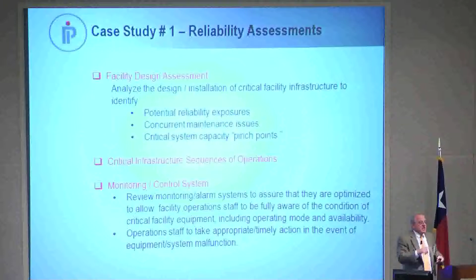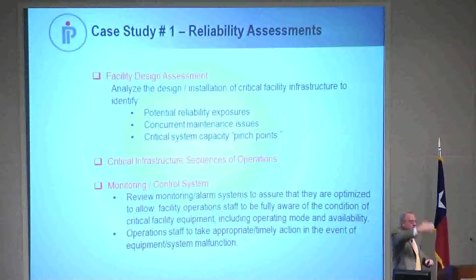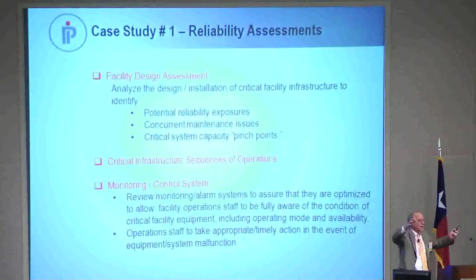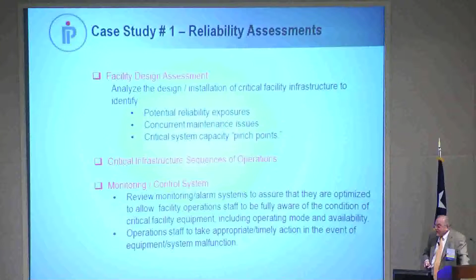It gives you an opportunity to review the sequences of operations and make sure that control package is working the way it should, and that while you've been gone for a year, nobody took everything out of auto and put it in hand because that was easier. Then you take a look at monitoring alarms and systems to ensure they're optimized so operations staff is fully aware of alarm notifications. Sometimes it's mind-boggling to go into a network operations center and find a list of 100 alarms that nobody has looked at, or they just clear them as a group. So the audit program looks at that kind of thing.